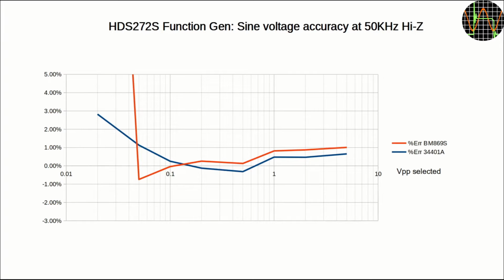In this plot, the selected volts peak to peak is on the x-axis, while the y-axis shows the percent error of the measured value against the equivalent RMS value. The BM869S test you just saw is the red curve, which is generally within plus minus 1% except for very small values of 0.02 volts peak to peak, where the error is way off.